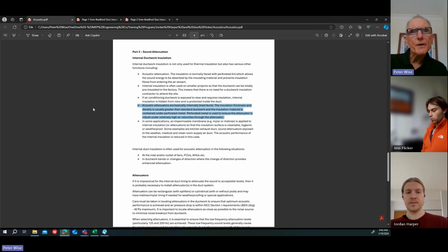Now, acoustic attenuators are basically internally lined ducts. The insulation thickness and density is usually greater than the standard ductwork, and the insulation material is contained under perforated metal in this case, not perforated foil. They use perforated metal to ensure the attenuator, or the insulation, is robust under relatively high air velocities through the attenuator. We'll talk about this a bit more in a minute, but velocities through the attenuator can be quite high, up to around 15 meters a second.